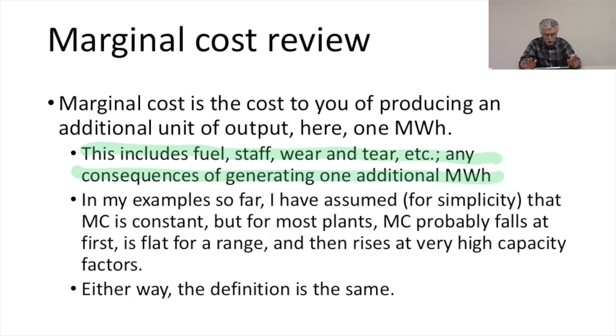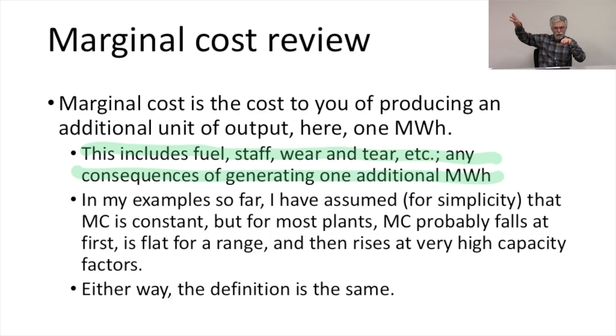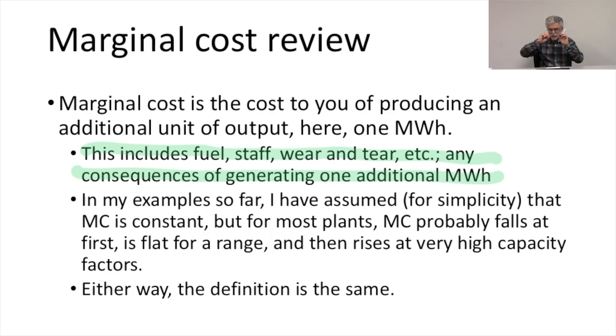In my example so far, I've assumed for simplicity that the marginal cost is constant for any capacity factor for the power plant — whether you run it full tilt or just a little bit. For most power plants, this probably isn't right. Marginal costs likely fall at very low capacity factors as you increase toward their ideal operating range, and then can rise again if you push them too hard — running them through maintenance periods instead of turning them off.